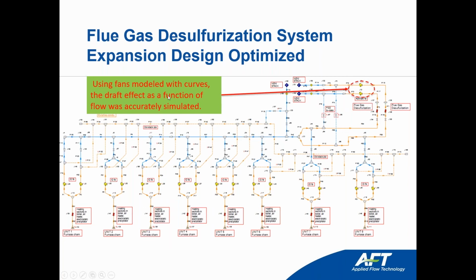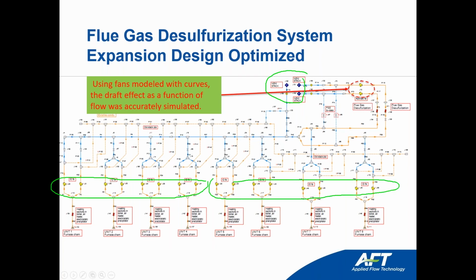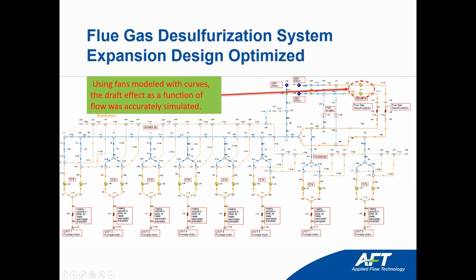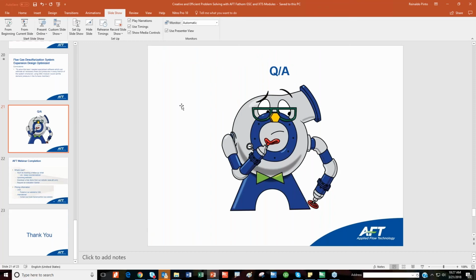So here's the plant, and here is where the fans were modeled with curves, and the drafts with curves to simulate the draft effect as a function of flow, and accurately simulated. So here we have the new stacks. These are the 4 plants that were the old ones for the desulfurization system, and this is for the ones that are going to be added.